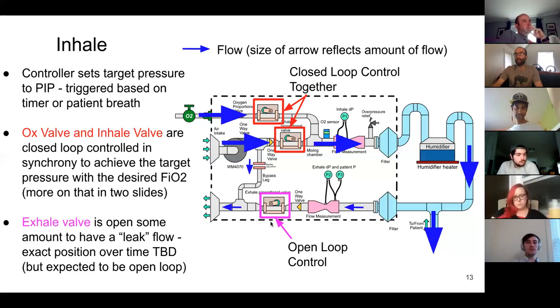And then during inhale, this control valve, when this was a solenoid, was just bang, 100% closed. With the pinch valve, there might be some leakage, which just establishes the bias flow to ensure that flow always is going one way through the ventilator and nothing ever comes back through the wrong leg. But with this very small leakage here, we're able to build up pressure really rapidly, and that's what drives flow into the patient.